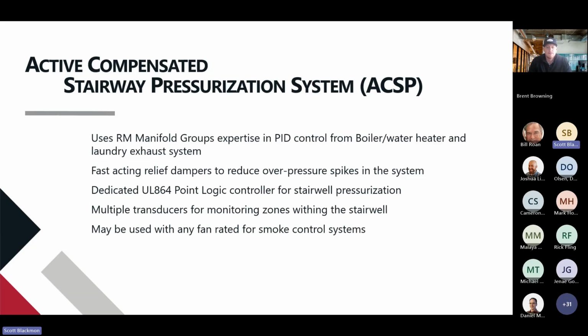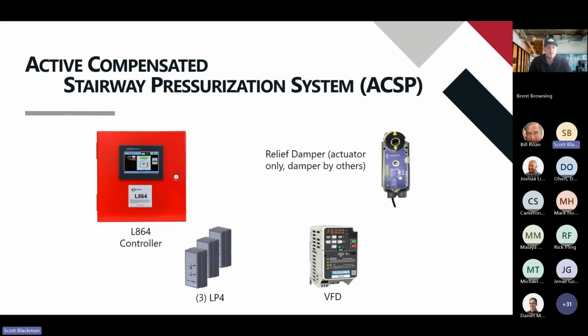The other nice feature is it's plug and play. So it consists of a point logic controller, 3 pressure transducers, a VFD, and a relief damper actuator if needed, if you've got a relief damper in there. The reason we want to use our actuator is that it's proprietary to us, and it's a 2-second modulating actuator. So it's 2 seconds fully open to fully closed, and it can modulate, so we can react to changes in pressure very, very quickly with that system.